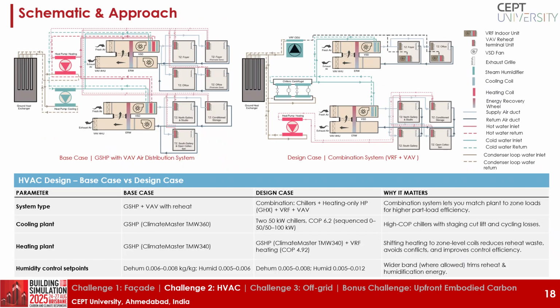In the base case, the system was modeled as a ground source heat pump with a variable air volume distribution system. The ground heat exchanger consisted of 27 boreholes, each 150 meters deep. Two heat pumps were provided to handle both cooling and heating with full humidity control and heat recovery. Air distribution was managed through two AHUs, one serving the display area and condition storage and the other serving the foyer and office, allowing more efficient fan control.